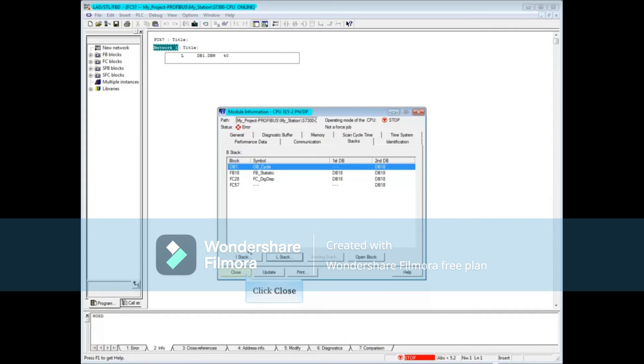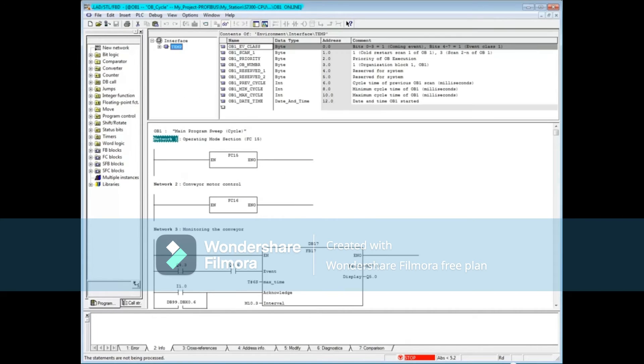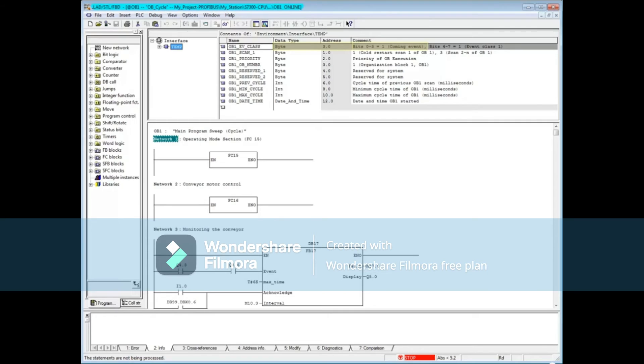Let's pull down the divider window in OB1. Here in the temp variables of the interface is the local data stack where the values you saw earlier were read from. We saw that byte 0 had a 11 in it, which means that there was an incoming event of event class 1. You can find more information about the local data stack of OB1 and the other OBs from the Simatic help on OBs.